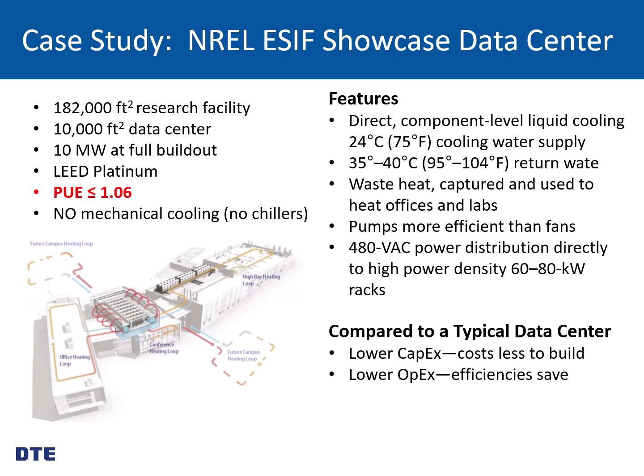No chillers, and some water cooling, and I'll share a few photos. So they're using some pretty advanced technologies, but the cost savings from no cooling towers and no chillers might be substantial. Here they do have evaporative towers, but you could have dry coolers. If you have a body of water, a lake, or a river, you could potentially use that for your cooling source.